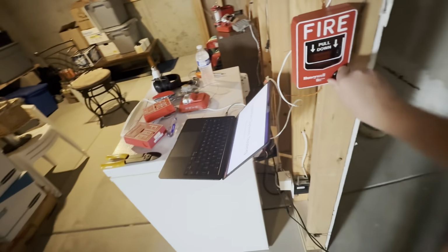So you got the fire alarm. That is zone 5, which means that station is working properly, and no other pull stations are pulled. So see, this is on zone 5, and this is on zone 5, and they're normal, which means this one is the culprit. And we'll confirm that by resetting the pull station and resetting the fire alarm control panel. Should not go off. Okay, there you go.